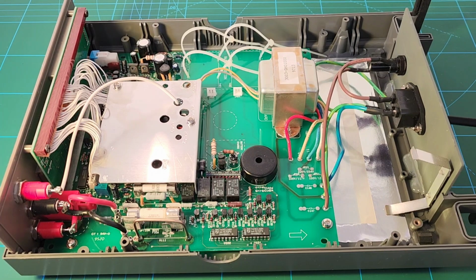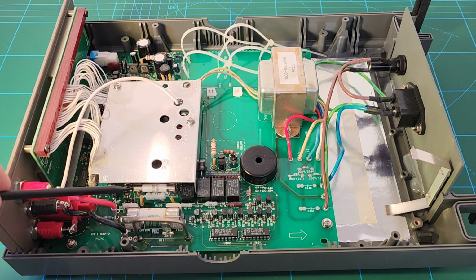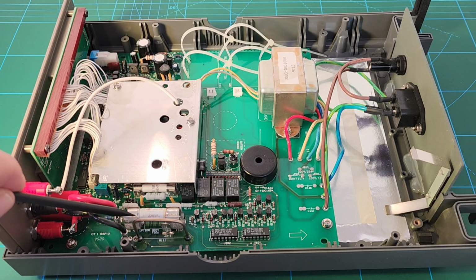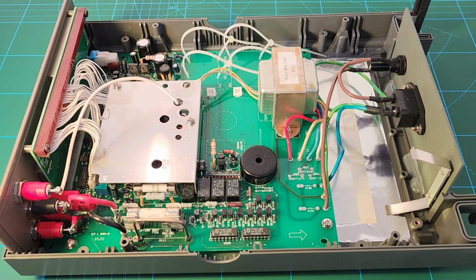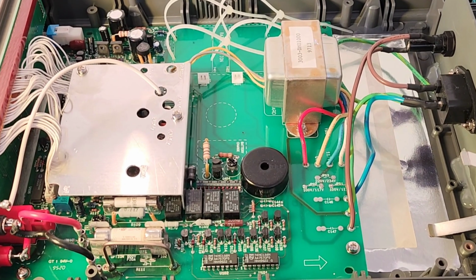Okay, let's start off with the back of the unit here where the 120 volts comes in. We have our one replaceable fuse here on the milliamp side. Now that you could do without removing the housing. If you had to change your high current fuse or your low current, there they were. And look at the size of that massive HRC over here. Unbelievable. It is massive. If you take a good look as well, what do you see?